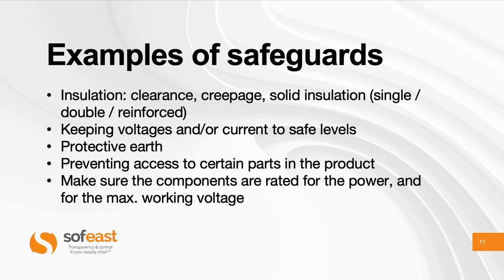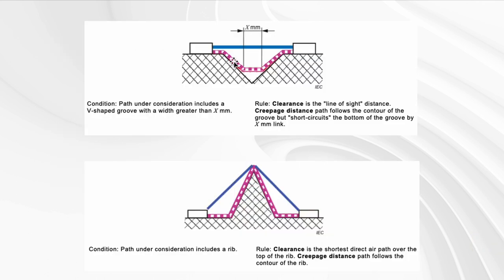So what kinds of safeguards are typically used? Of course, insulation — and clearance and creepage. For a groove or rib like this, it makes the difference obvious. The blue one is the clearance, which is the air gap between two poles — for example, high and low — separated by air. The clearance is calculated as the shortest direct air path.